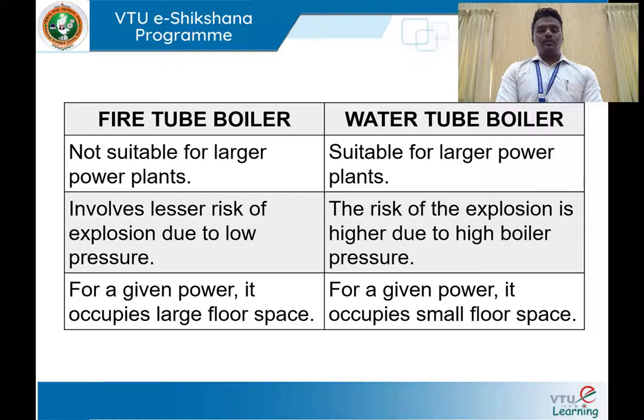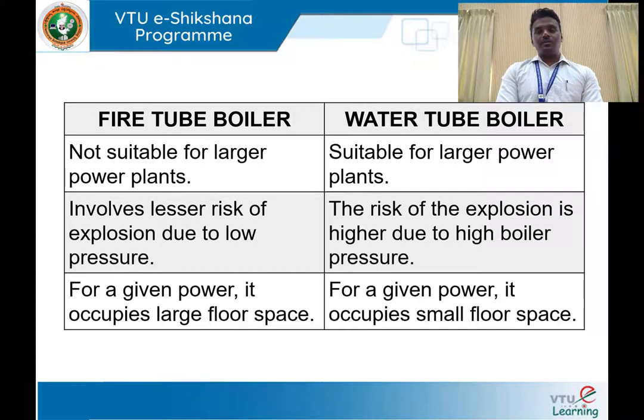The fire tube boiler has lesser risk because of steam generation at lower pressure — there is less chance of explosion. In the water tube boiler, since operating pressure can go up to 100 bar, there is a chance of explosion if proper safety measures are not taken. The fire tube boiler occupies a large floor area, while the water tube boiler, for a given steam generation capacity, occupies a smaller floor area.